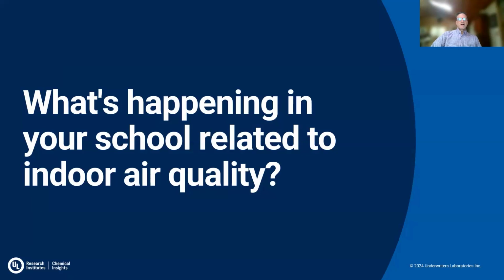Thanks, Holly, that's a really great question. After COVID, the ESSER and FEMA fund granting allowed us to make changes to our HVAC. We were able to increase our air filtration to MERV 13, which is a minimum efficiency reporting value, removing 75% of the airborne virus. We have a schedule to maintain the filters and change them based on the manufacturer's recommendation. The increased minimum classroom air changes were made to 6 per hour, and even higher in our music room, around 10 air exchanges per hour.